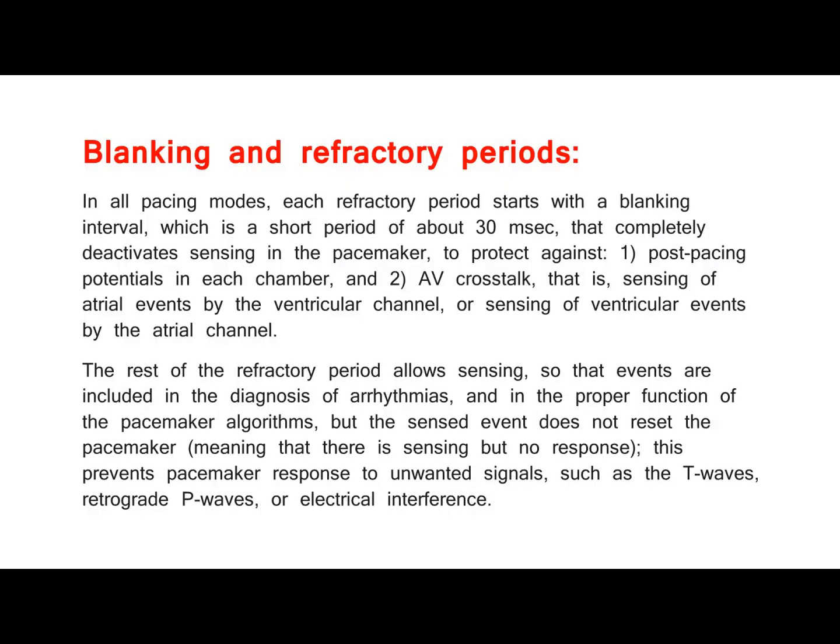Blanking and refractory periods. In all pacing modes, each refractory period starts with a blanking interval, which is a short period of about 30 milliseconds, that completely deactivates sensing in the pacemaker, to protect against 1. Post-pacing potentials in each chamber, and 2.